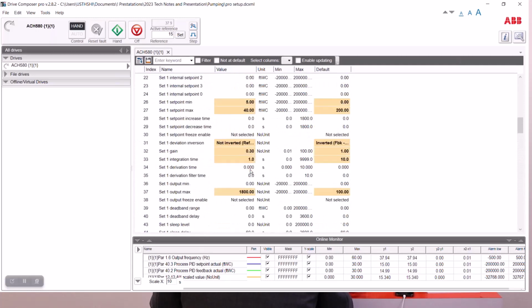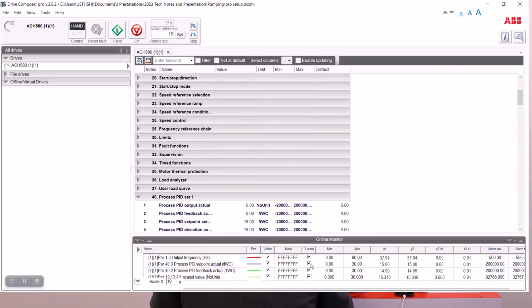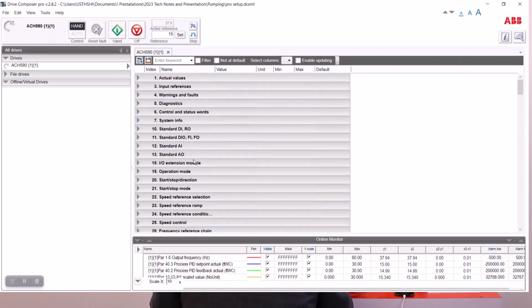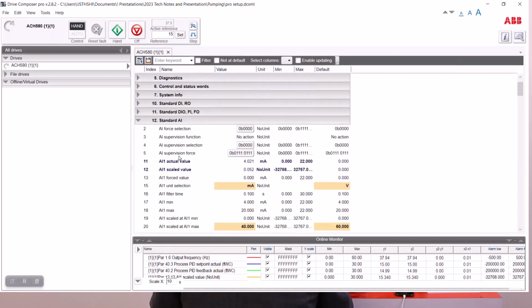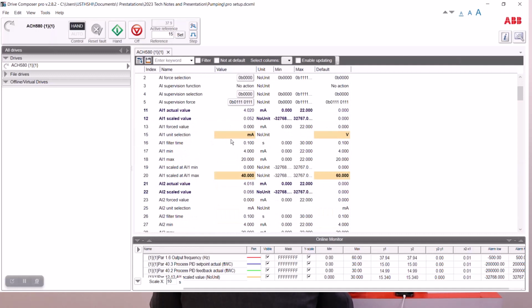One other thing I'm looking at when I look at my settings in here, so my chart down here, is I have the analog input set up, so AI1. I've set up AI1, which is a 4-20 milliamp input, and I have it set up as a scaled input. So right here is my AI1 scaled. This is what the meter's reading. Right now, statically, the meter's reading 0.052.